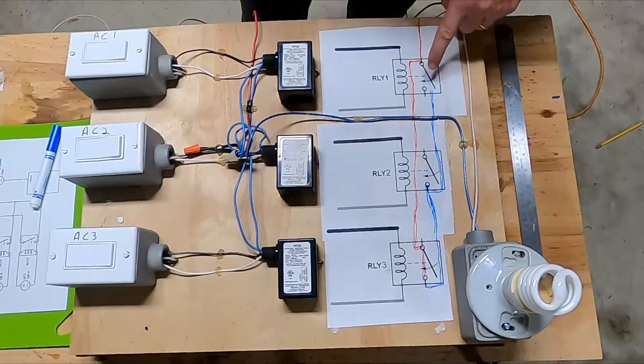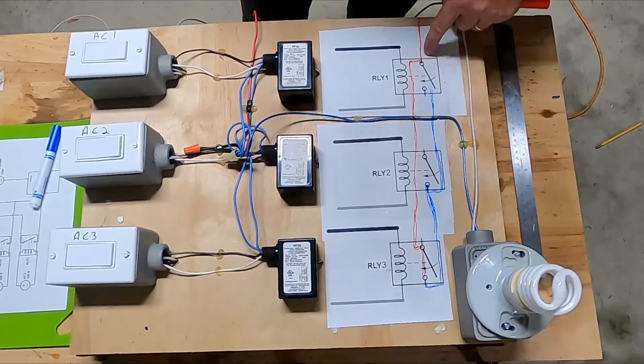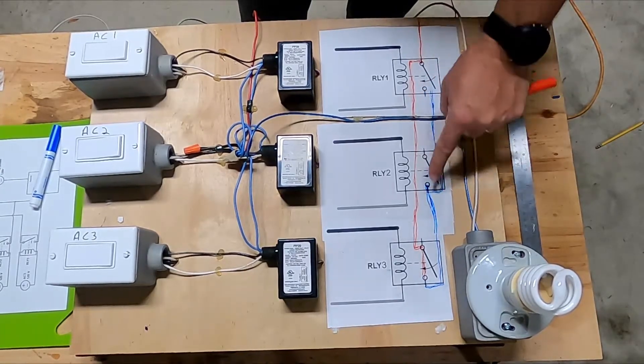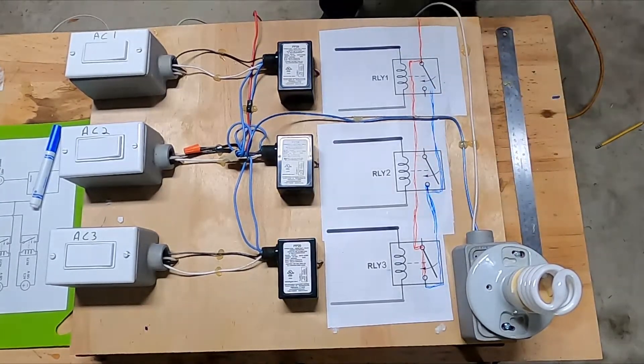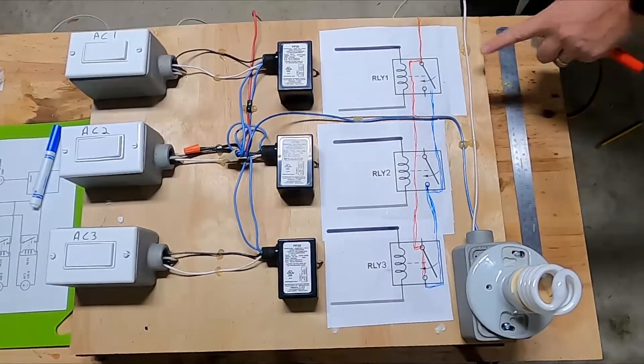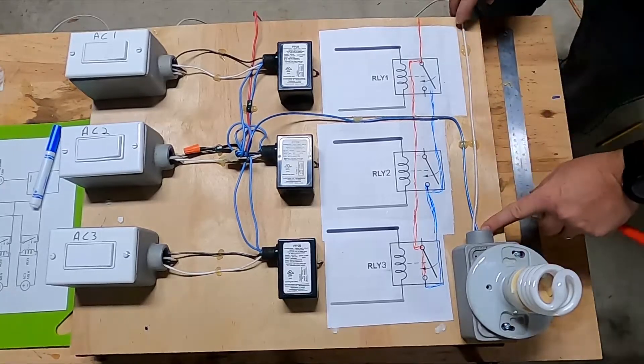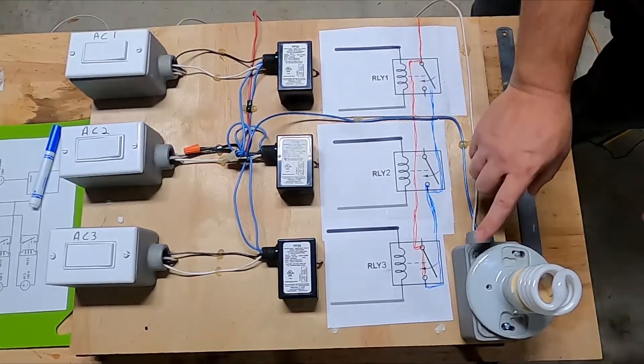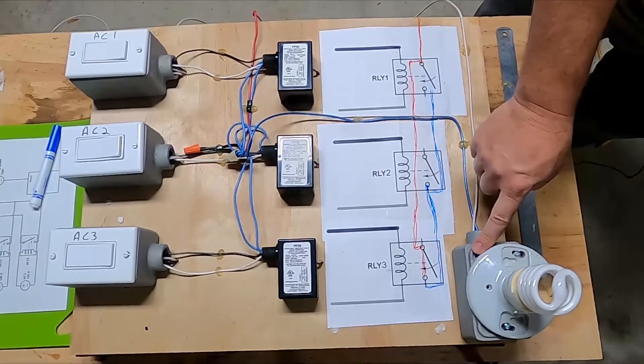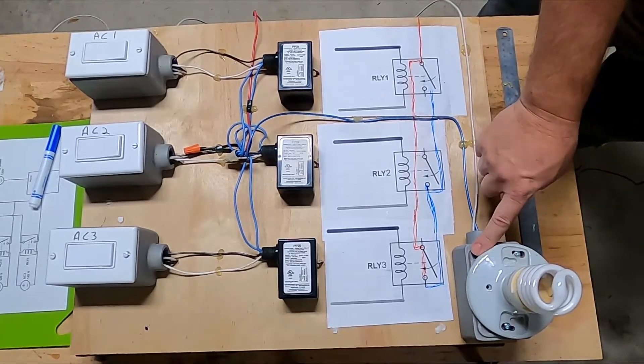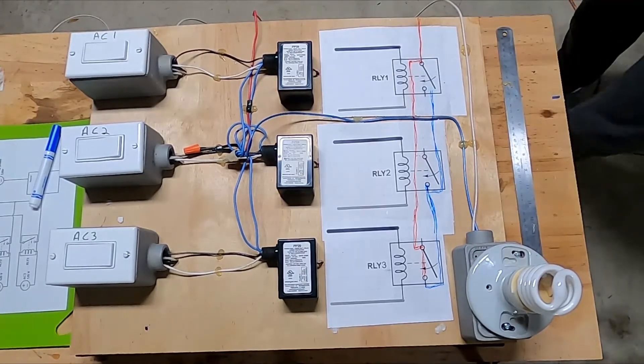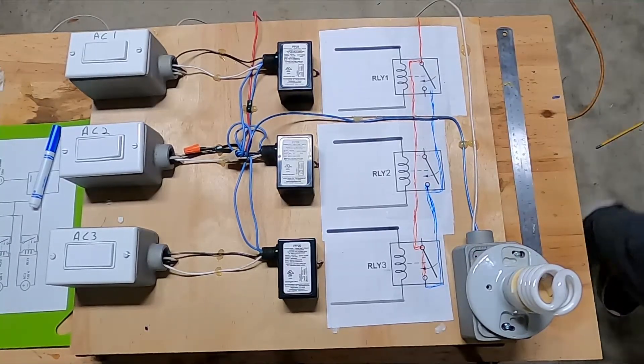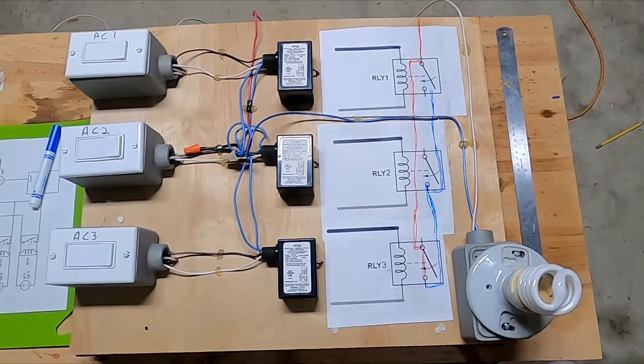You don't need a neutral on the contact side of the relay. So your neutral is going to be independent. That just goes straight to your motor, to your load.